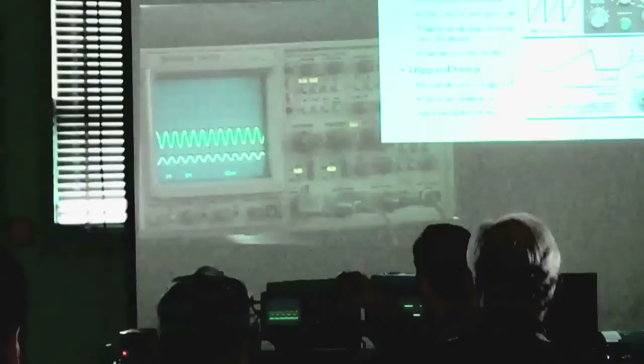Let me show you the example here on the scope. So look at the screen here. If I set this up, this thing kind of focuses. We can see this is going at 10 microseconds per division. If I take my variable, you can see I can actually adjust this and go slower. This particular scope will actually show me a calibrated value. Most scopes don't have the on-screen display, so you don't know where you are. We have a time mark generator back here that will make a little signal, so there's an example we'll be able to use to look at that. You'll notice I can adjust this all the way down to 30 microseconds per division, and if I go back up to where I calibrate, if you listen carefully, click, now I'm in the calibrated position.